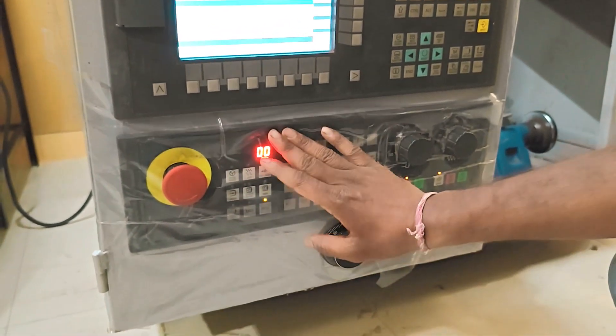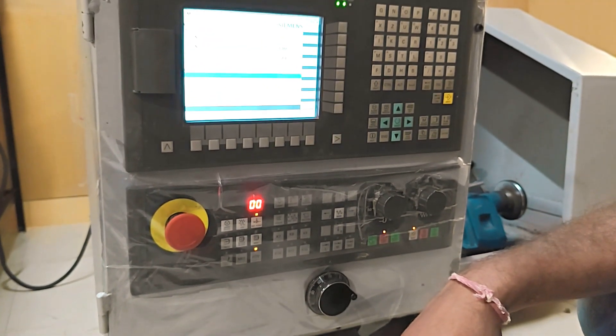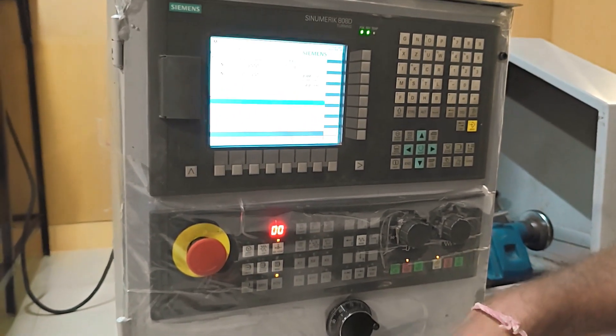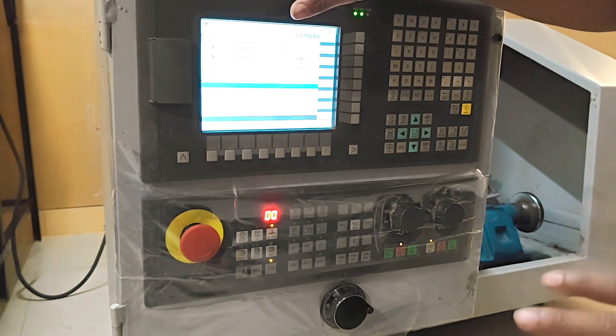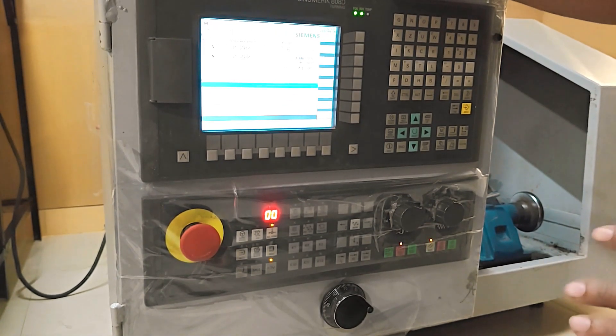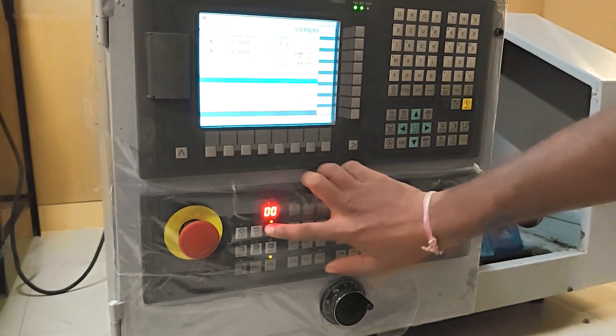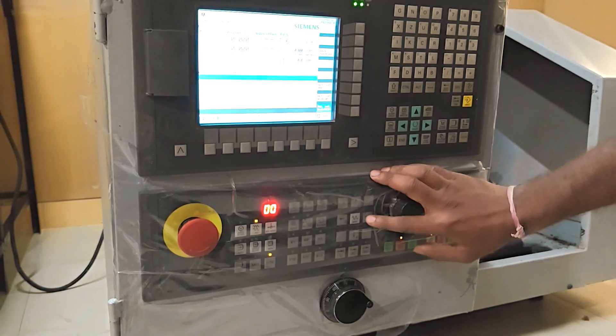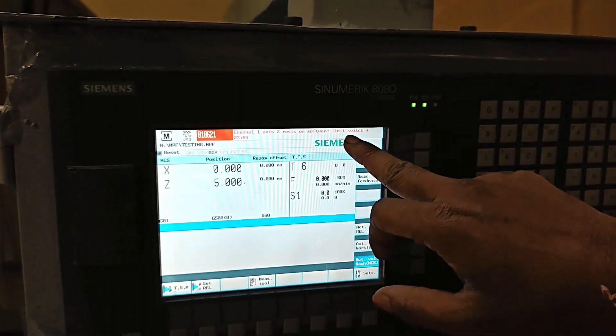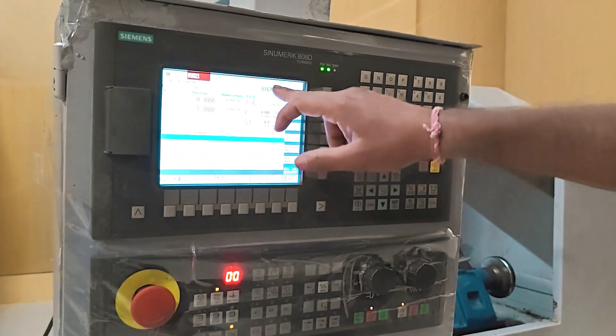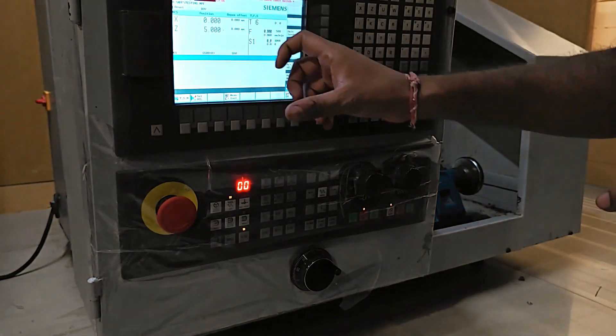If some error is coming, how do we clear it? At machine startup, the common message is 'reference not done' — it's a message, not an alarm. If someone unknowingly moved the axis in jog mode to a minus position, the Z-axis may hit the soft limit. This is a soft limit, not a hard limit.